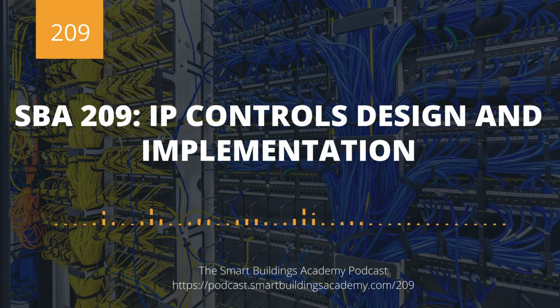Bus is kind of middle of the road. It's very similar to how we wire up the daisy chain for our MSTP token ring. You essentially have one wire that comes out of the switch port on the switch. It goes to the first controller and plugs into the first controller's network interface card, and then that controller will have two network interface cards, and it will then have an Ethernet cable that goes from that controller to the next controller in a daisy chain pattern.